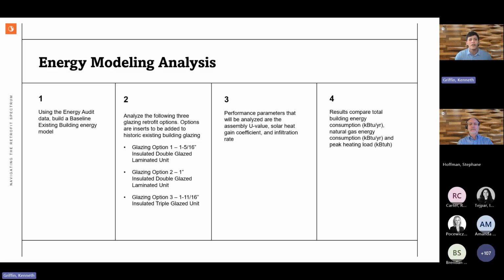We used the data from our energy audit, built an existing building model, and analyzed three types of glass: two types of double glazing inserts and one type of triple glazing insert. We looked at U values, solar heat gain coefficient, and infiltration rate, because we were feeling issues with the air. There was also a blower door test done, and we saw huge CFM per square foot per Pascal infiltration coming into the building, which made sense based on what we were feeling.